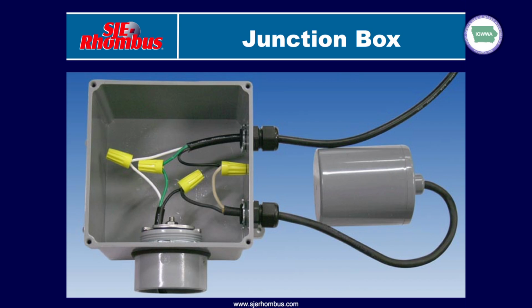On the pump switches, in addition to having a piggyback option, more often than not on effluent pumps or sewage pumps, a lot of times we're going to see the connection hardwired in a junction box. We want to make sure if we are hardwiring the connection for an outdoor installation that we use a weather-tight junction box, like what you see there. And on the lines that go out to the sewage tank or out to the pump tank, we want to make sure we have some sort of sealant to keep sewer gas from getting into our junction box.